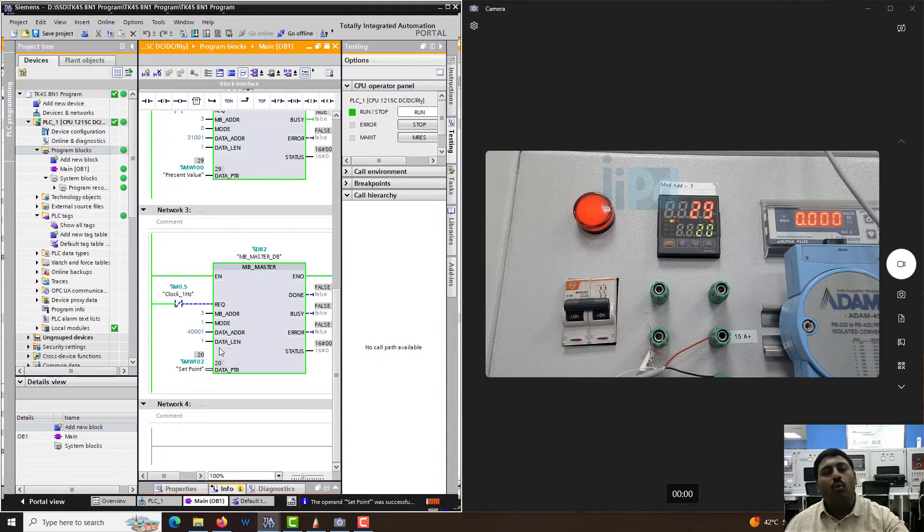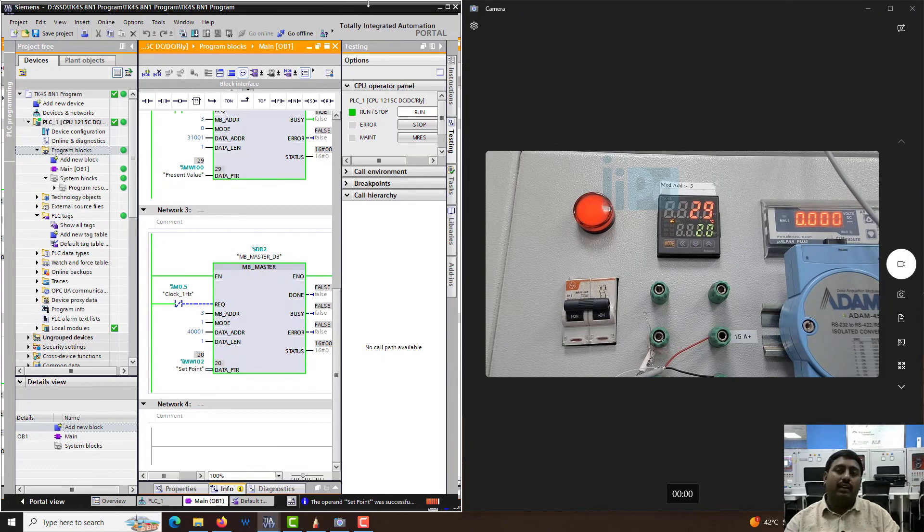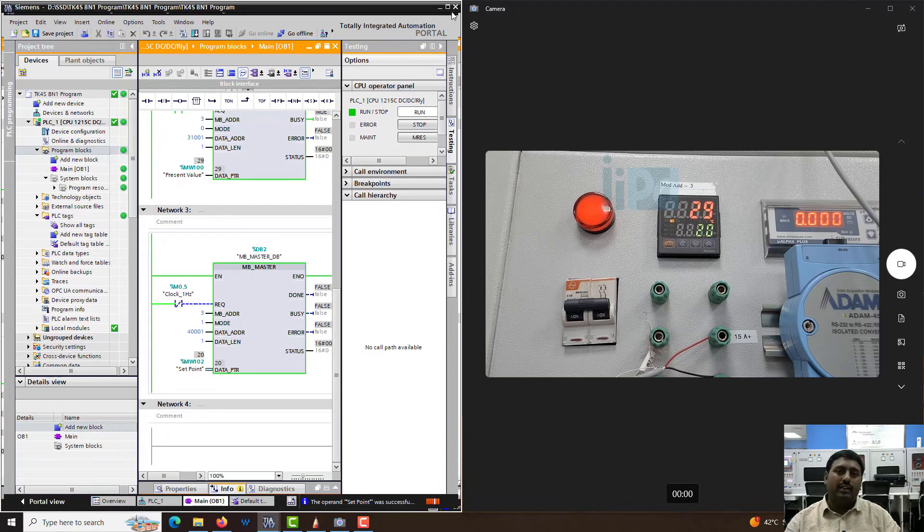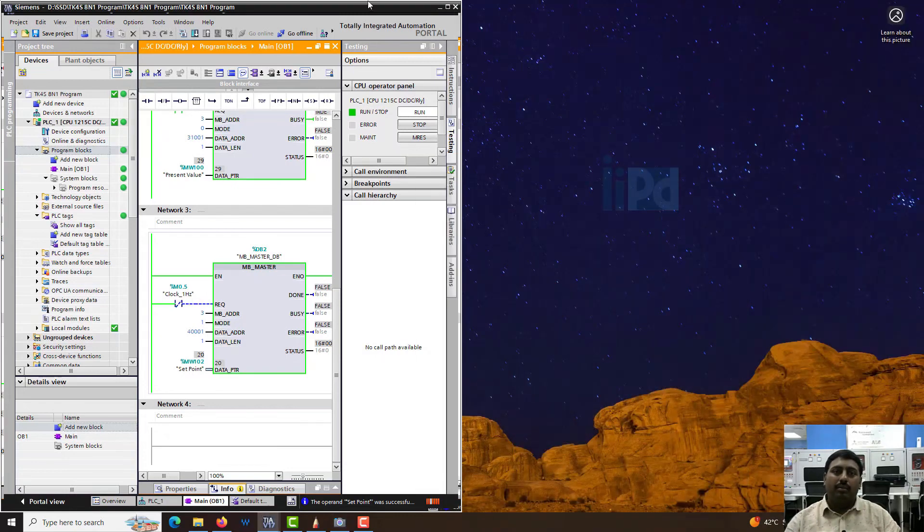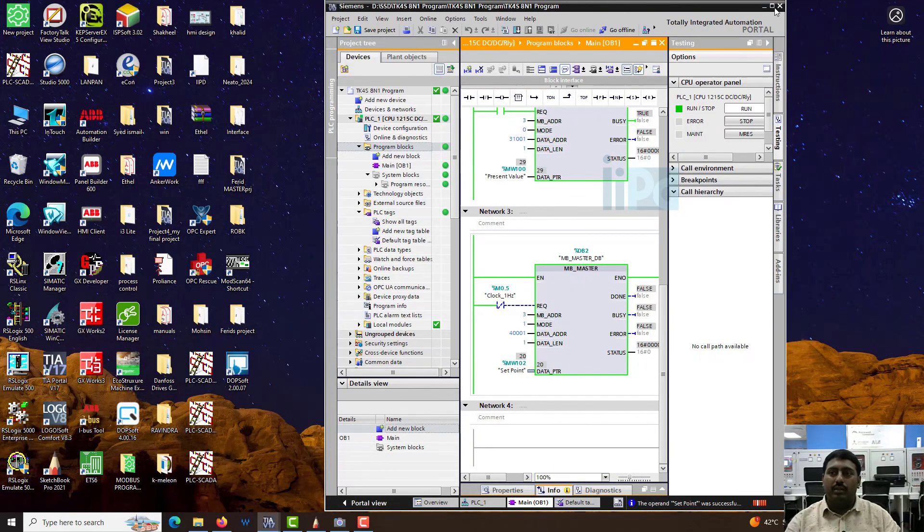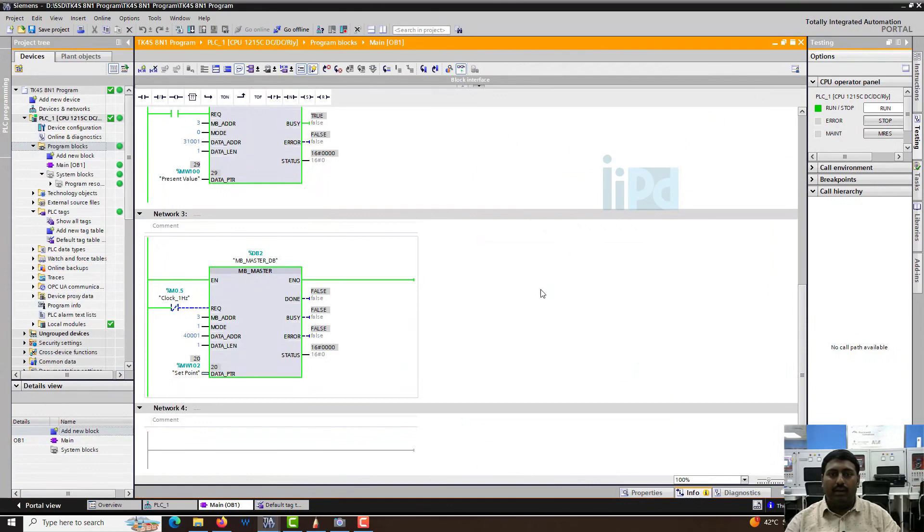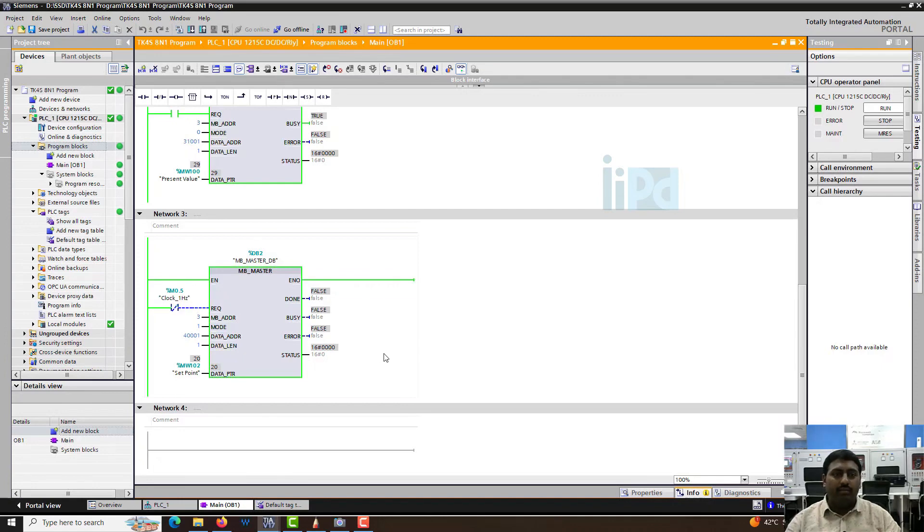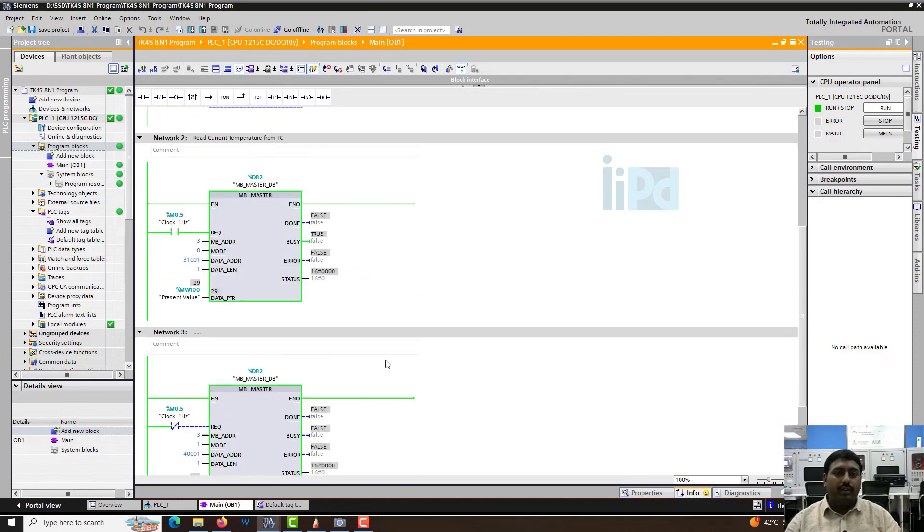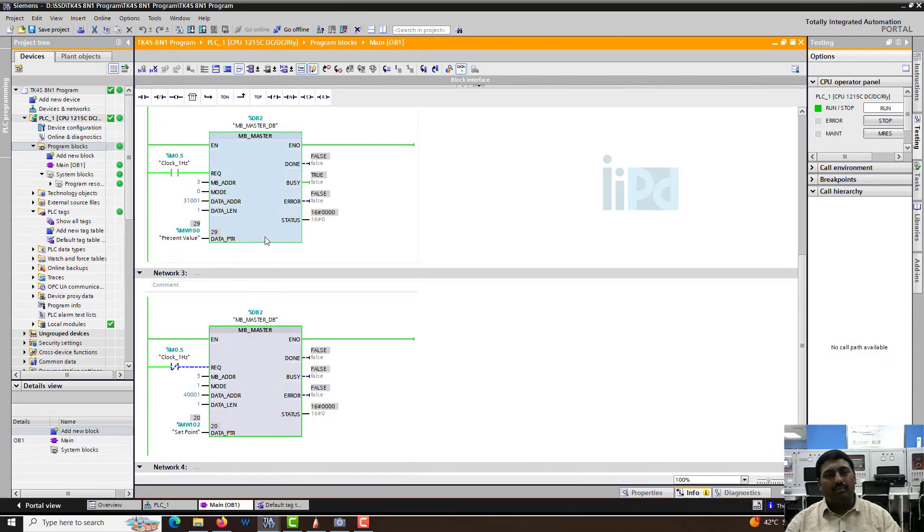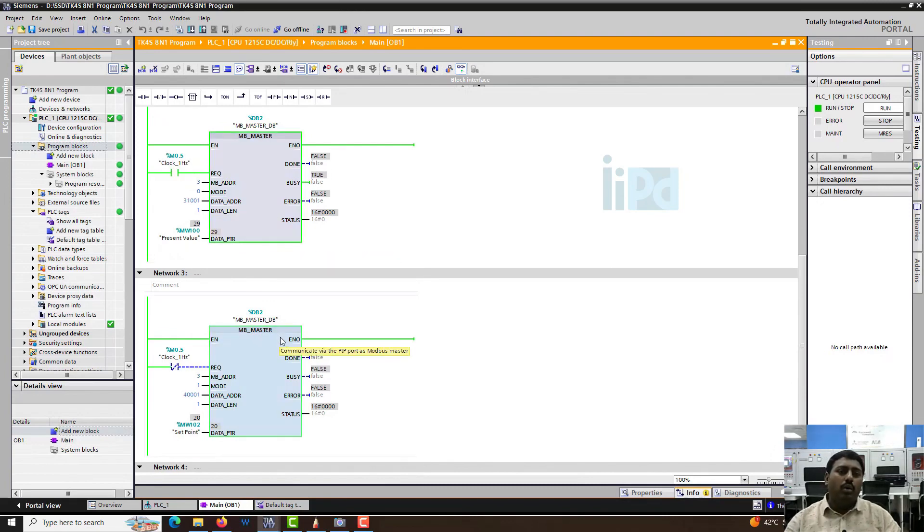This is how we read the data from the PLC. There is one more caveat here. Sometimes this will also give you some error. Sometimes doing this might give you an 8189 error or 8200 error, which means you are trying to send and receive request at the same time. How to avoid this? It's an easy way.